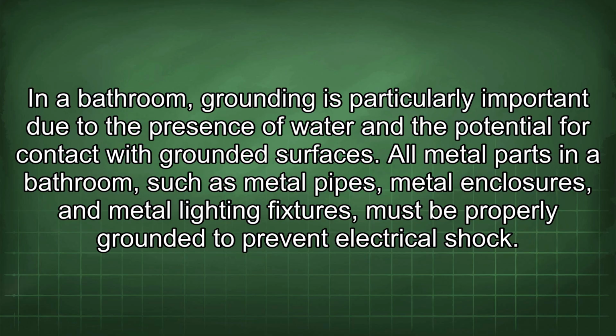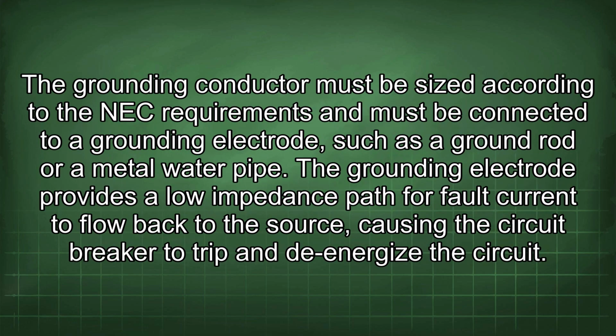In a bathroom, grounding is particularly important due to the presence of water and the potential for contact with grounded surfaces. All metal parts in a bathroom, such as metal pipes, metal enclosures, and metal lighting fixtures, must be properly grounded to prevent electrical shock. The grounding conductor must be sized according to the NEC requirements and must be connected to a grounding electrode, such as a ground rod or a metal water pipe. The grounding electrode provides a low impedance path for fault current to flow back to the source, causing the circuit breaker to trip and de-energize the circuit.